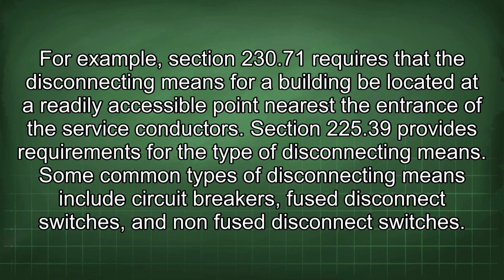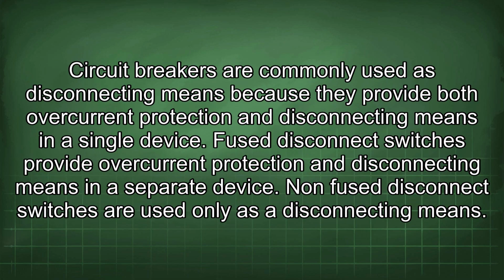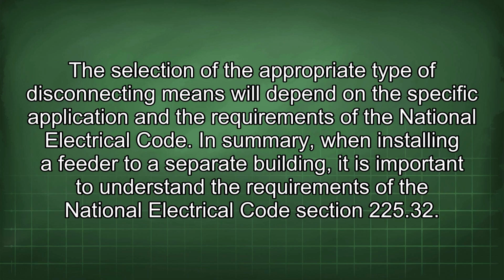Some common types of disconnecting means include circuit breakers, fused disconnect switches, and non-fused disconnect switches. Circuit breakers are commonly used as disconnecting means because they provide both overcurrent protection and disconnecting means in a single device. Fused disconnect switches provide overcurrent protection and disconnecting means in a separate device. Non-fused disconnect switches are used only as a disconnecting means. The selection of the appropriate type of disconnecting means will depend on the specific application and the requirements of the National Electrical Code.